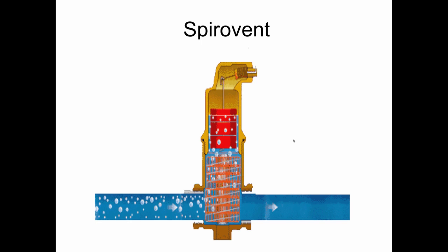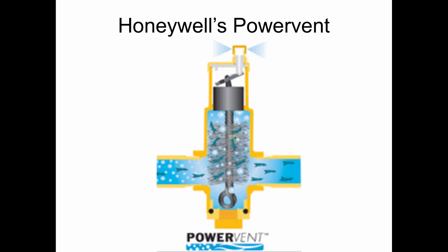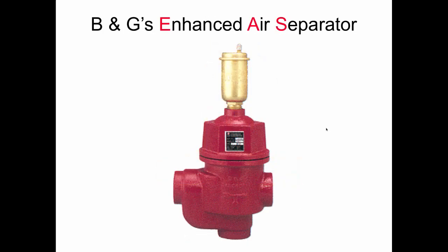Any air separator will get rid of the air eventually if it's installed properly in a closed hydronic system. Honeywell bought from a company called Sparco this air separator and renamed it the Power Vent — it's similar to the Spirovent but, not being able to use that proprietary element, they decided to use a fitting brush. I love this — if you can make an air separator out of a fitting brush, it just goes to show that if you can't make money in America you're just not paying attention. Bell and Gossett also came out with their wonderfully named Enhanced Air Separator, which also has a fitting brush inside, and it works pretty well too.